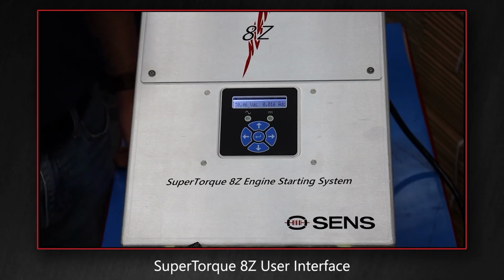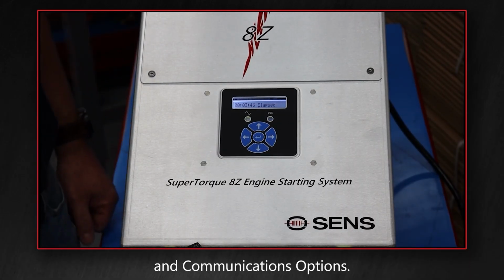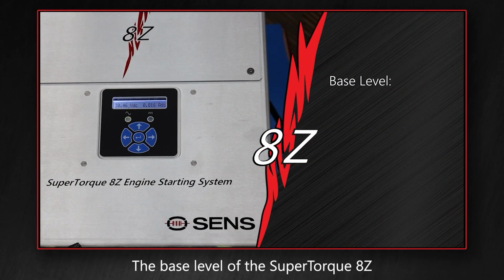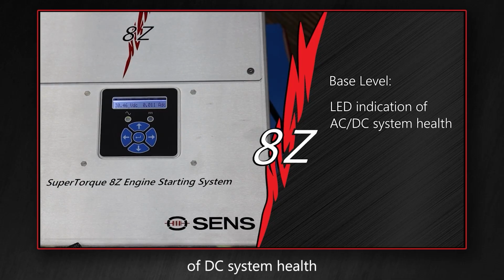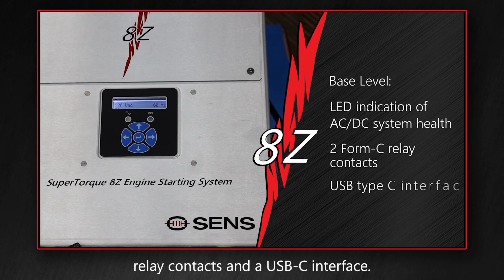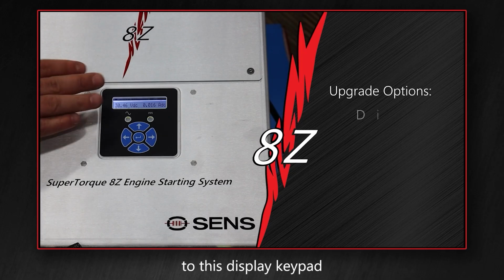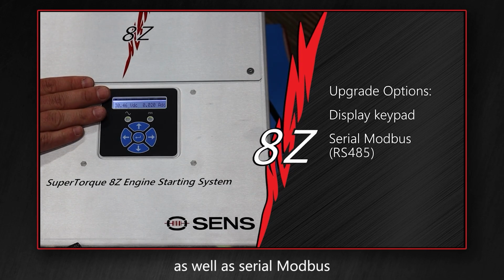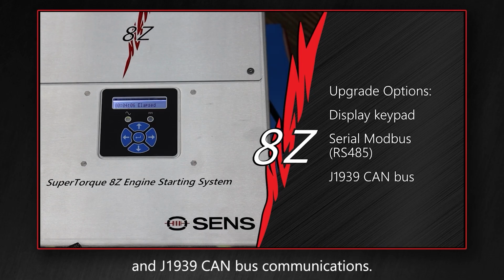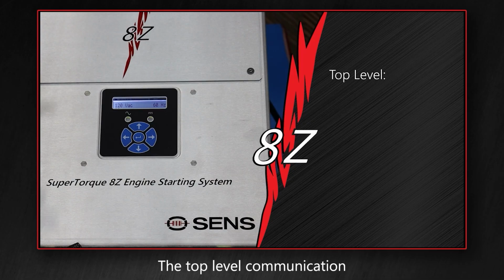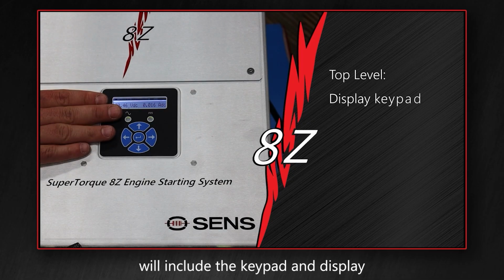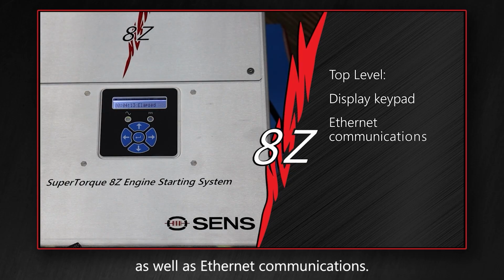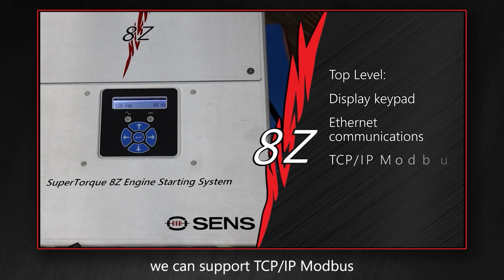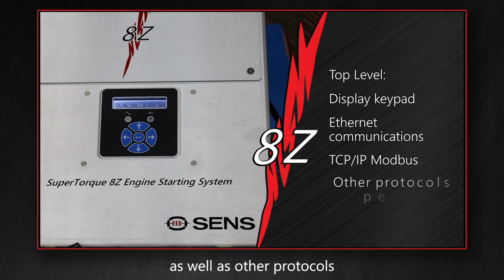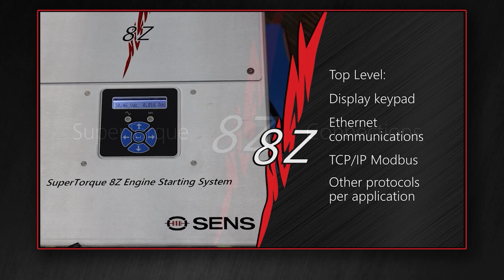So looking now at SuperTorque 8Z user interface and communications options. The base level of the SuperTorque 8Z will have LED indication of DC system health and AC system health, as well as Form C relay contacts and a USB-C interface. We can then upgrade to this display keypad, as well as serial Modbus and J1939 CAN bus communications. The top level communication and interface package will include the keypad and display you see here, as well as Ethernet communications. And on Ethernet, we can support TCP/IP Modbus, as well as other protocols as needed in the application.